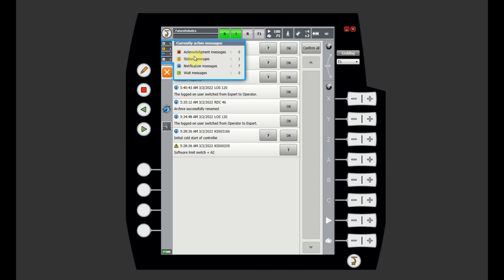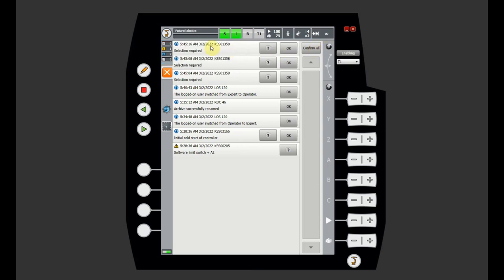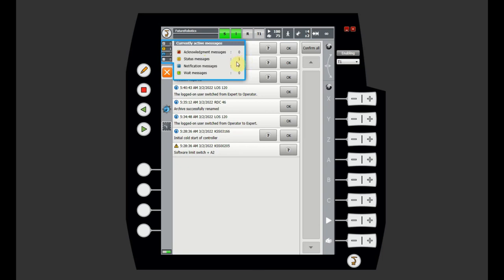There are acknowledge messages, status messages, notification messages, and wait messages. You can see how many notifications or messages you have. Acknowledge messages with the red X icon will prevent you from running the robot — you need to fix what happened and clear the message by clicking OK or Confirm All. Status messages are similar: you cannot clear a status message while the condition is still happening. For example, a software limit switch on axis 2 — as long as the robot is hitting that limit, you won't be able to clear that message.